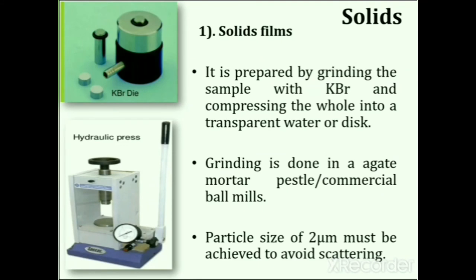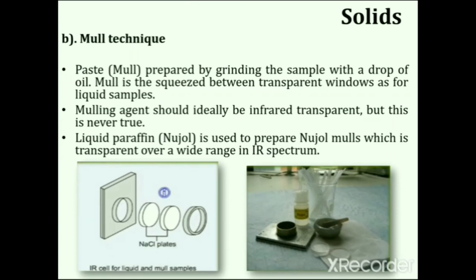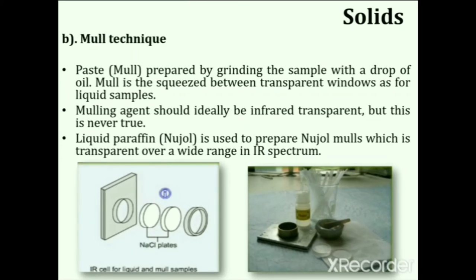Grinding is done in an agate mortar and pestle or commercial ball mills; poorly ground mixtures lead to discs that scatter light rather than transmit it. A particle size of 2 µm must be achieved to avoid scattering. Compression to form a cohesive disc requires high hydraulic pressure. Solid samples can also be handled by the mull technique: a mull is prepared by grinding the sample with a drop of oil, then squeezed between IR transparent windows. The mulling agent should ideally be infrared transparent. Usually liquid paraffin (also known as Nujol) is used, which is transparent over a wide range of the IR spectrum.